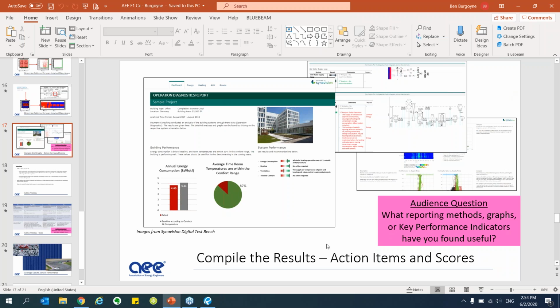A lot of these fault detection and diagnostic softwares facilitate uploading that data. In this case, we receive data, and the software takes you through a wizard. You input the data file, and you follow the wizard to detail where it should look for which pieces of information about the data. Where should it look in the file for the data point name, for the values, for the timestamp. And then in that software, you set up graphs and link them to these data points that you're uploading. They all have different capabilities for generating a report.